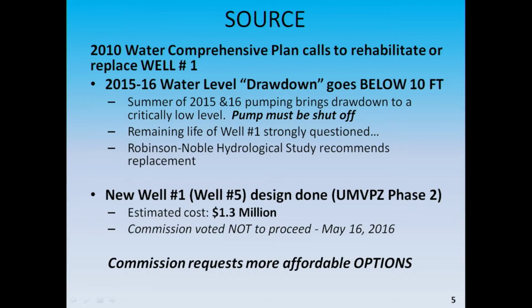In the last 2 years, especially last summer, and now we're experiencing it right now, when we turn on well 1, the drawdown of the static level to where it sits when running draws it down to within 10 feet of the pump head, and at that point we have to shut it off. We can't pump. That's actually been dialing down from 1,100 gallons per minute to slightly less than that, trying to allow that well to run as much as we can, but once that drawdown happens, we have to turn it off. We don't know what the remaining life is on well 1.